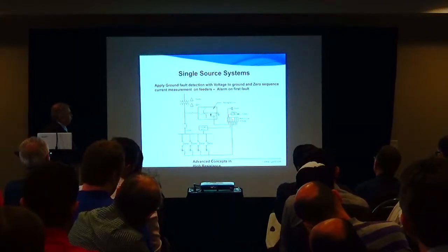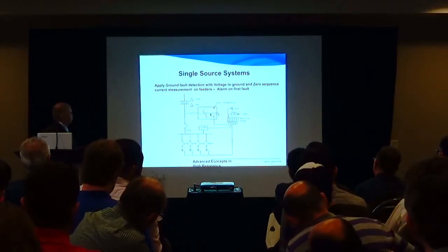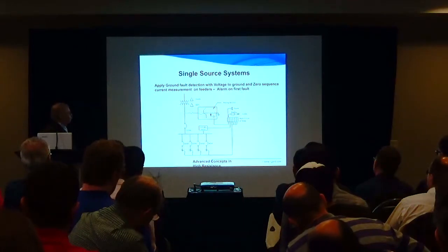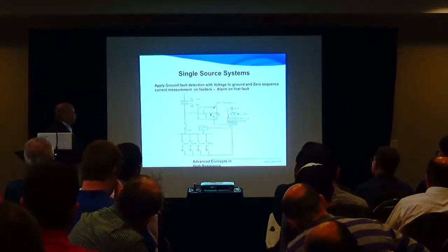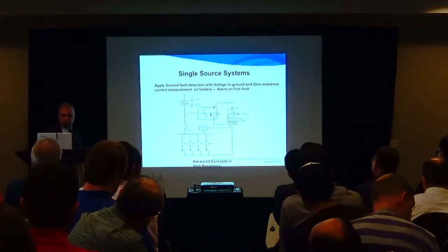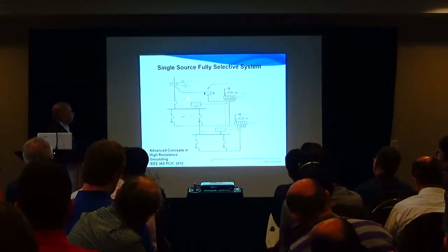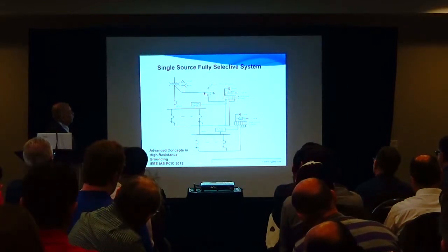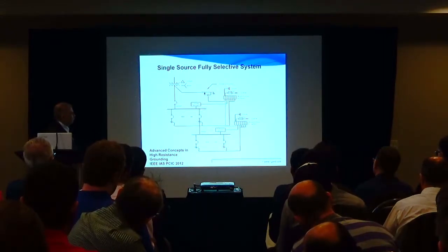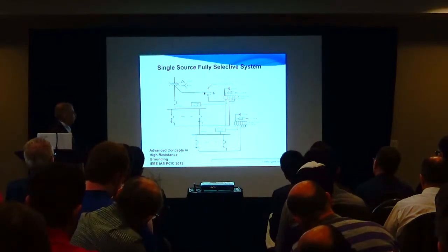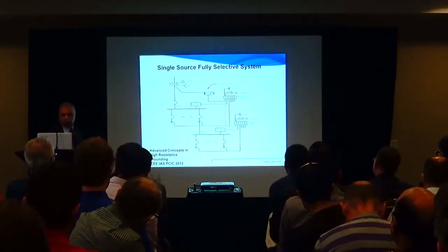And then a number of modules can be added to give you a larger system, up to 50 altogether on the one DIN rail with one power supply. And so this is not an expensive addition. All you needed was the zero sequence sensors and zigzag transformer with one relay. So the bus gets distributed among the feeders, and it is extendable. So if I have a three-stage distribution, then in this case I have a Y-connected transformer, so I need a grounding resistor, pulsing type to help me find the fault, then one DSP for this board, another DSP for this board, and they will communicate, and zero sequence sensors all over. So this is how these systems can be built to integrate into the distribution at various stages, right up to the load.